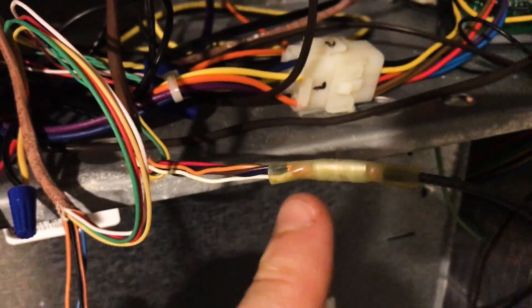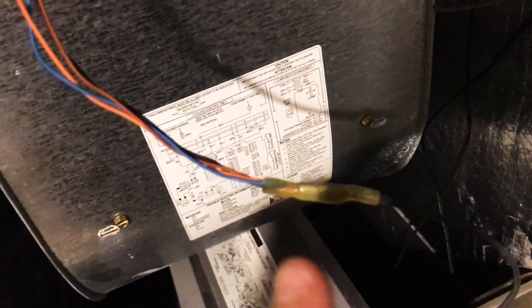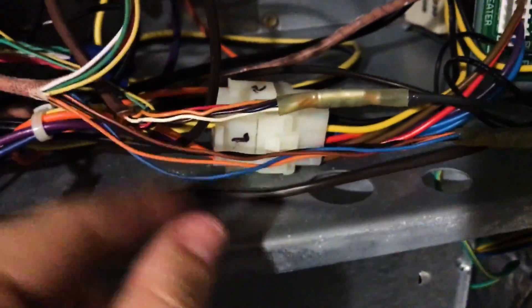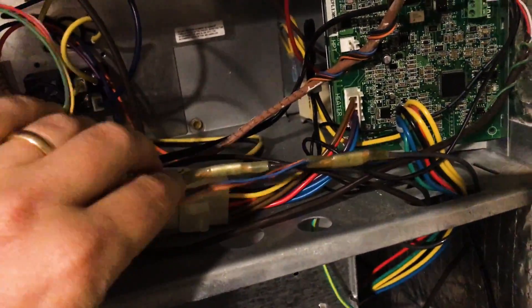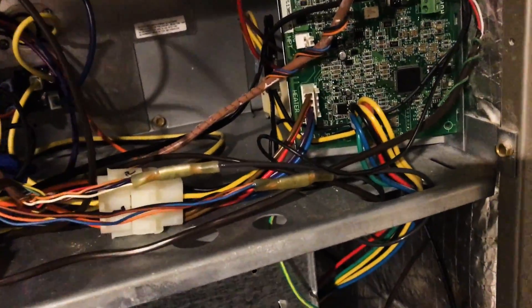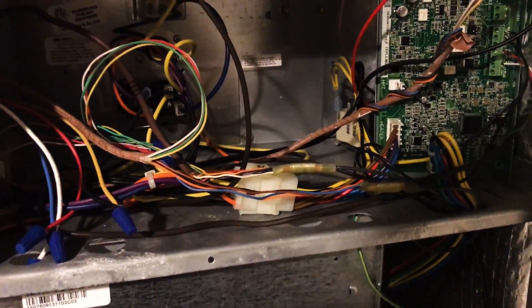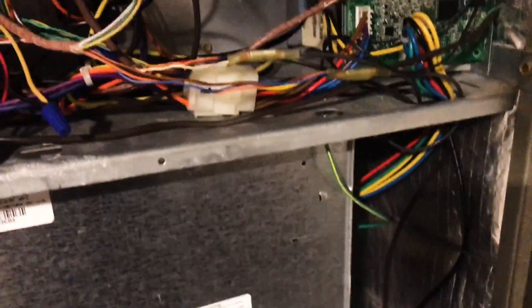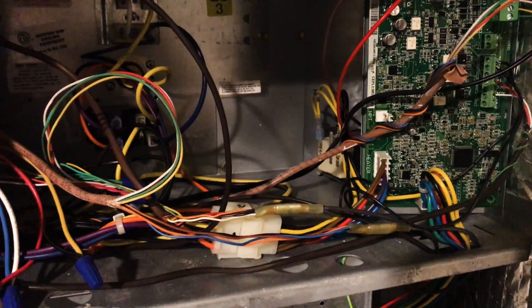If I was doing this on a conductor where I was worried about shorting, I'd keep the wires a little shorter. But this is definitely going to be a solid connection — all of our additional conductors butt-spliced together with number 14 stranded wire under a single ring connector. The idea is that any inductance or small signals picked up in the wire will be redirected harmlessly to ground on one side, rather than causing a communication fault. I'll report back on whether this fixes it, but in several cases where shielded cable should have been run but wasn't, this fix does serve the purpose. I'm Brian with HVAC School — thanks for watching.